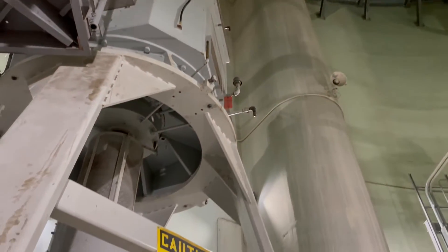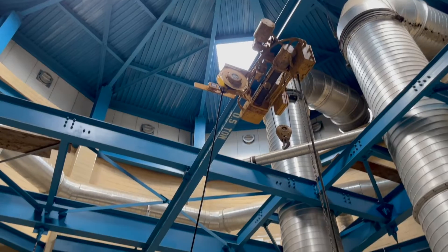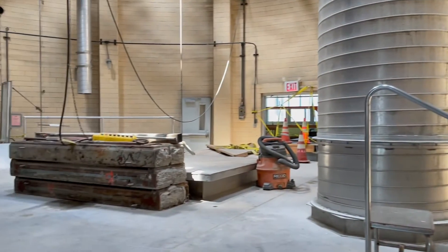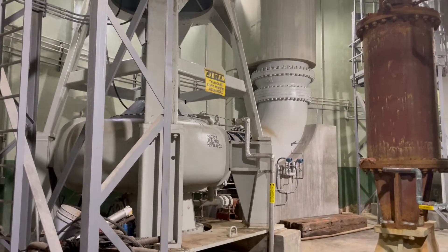There's really no moving parts in the wet well, but when we were down looking at the pumps below, there's a valve that separates the pump from the wet well. Valves aren't meant to last forever, and the only way you can replace a valve is by going into the wet well and plugging the large pipe that goes to the valve. So we took the hatch off the wet well, hired a scuba dive team — not your normal scuba divers, but the dirty job scuba divers. They went down while the plant was in full operation, in 60 feet of wastewater in a yellow basket, and hand-placed large blocks against the wall to provide a physical barrier between the wet side and the dry side. I did feel bad for the one guy whose suit leaked. And that's a testament to the folks that ultimately built and constructed the facility — this wet well has never been taken out of service, nor does it really have any way to be taken out of service.